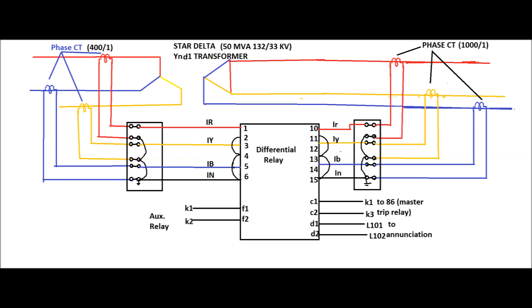In the case of a numerical differential relay, no ICTs are required for phase and amplitude matching — this is automatically done in the numerical algorithm. Only the relay current input from either side of the power transformer via the CTs is required, along with the rating data of the power transformer, the vector group of the power transformer, the HV and LV voltage rating, and the CT ratio of the HV and LV side.